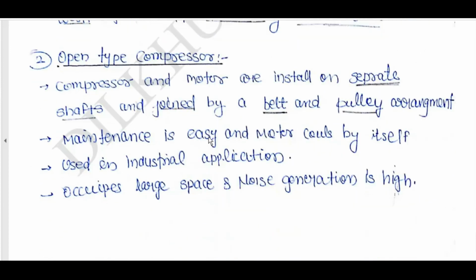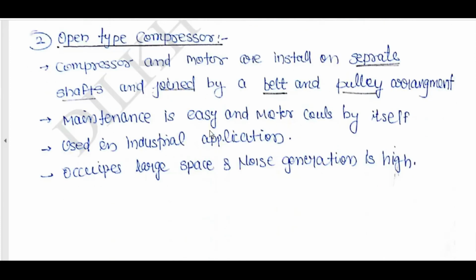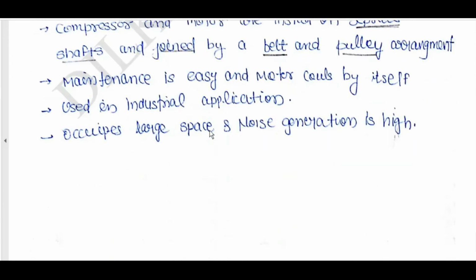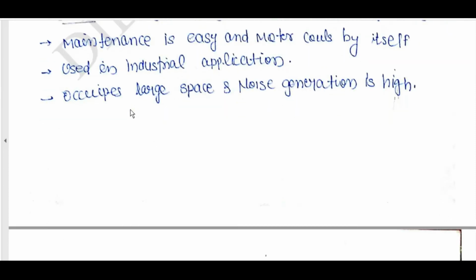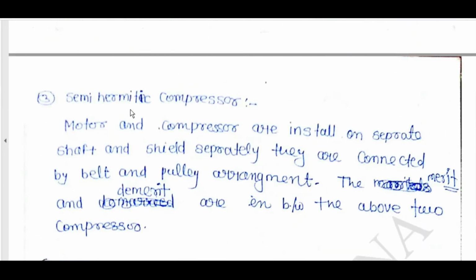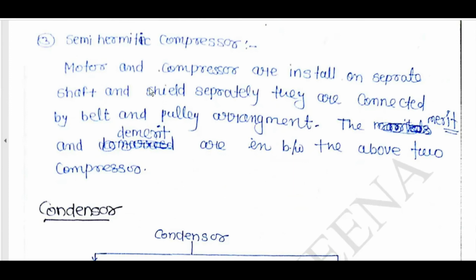Open type compressor. Compressor and motor are installed on separate shafts joined by a belt and pulley arrangement. Maintenance is easy and the motor cools by itself. Used in industrial applications, occupies large space and noise generation is high. Semi-hermetic compressor: motor and compressor are installed on separate shafts and shielded separately. They are connected by a belt and pulley arrangement. The merits and demerits are in between the above two compressors.